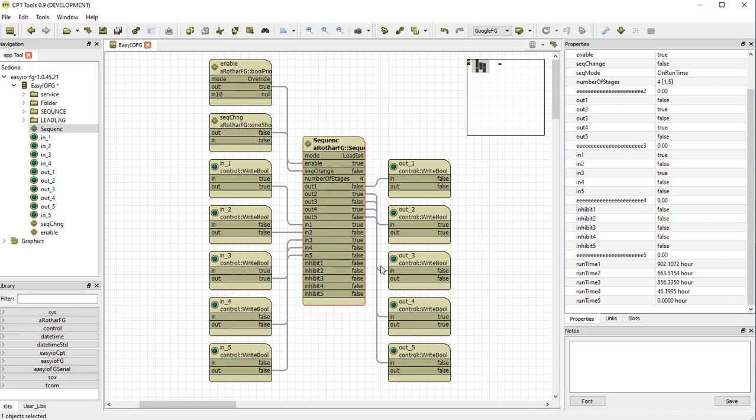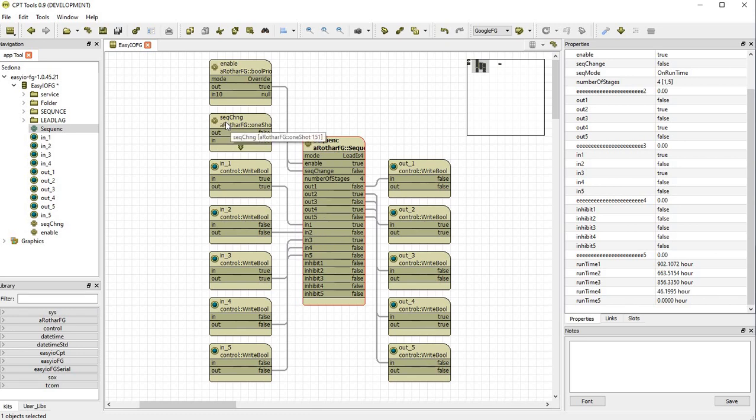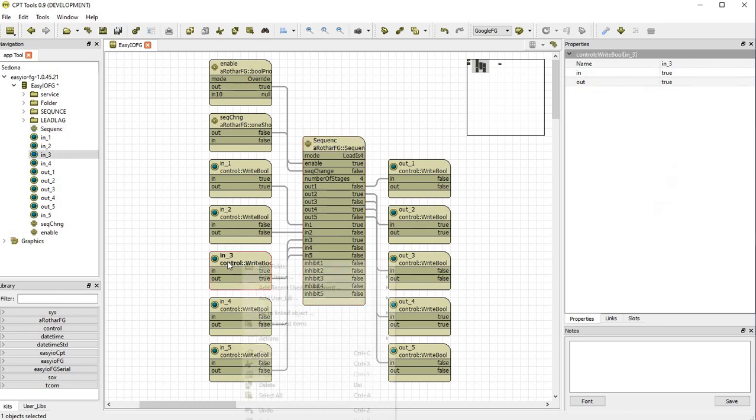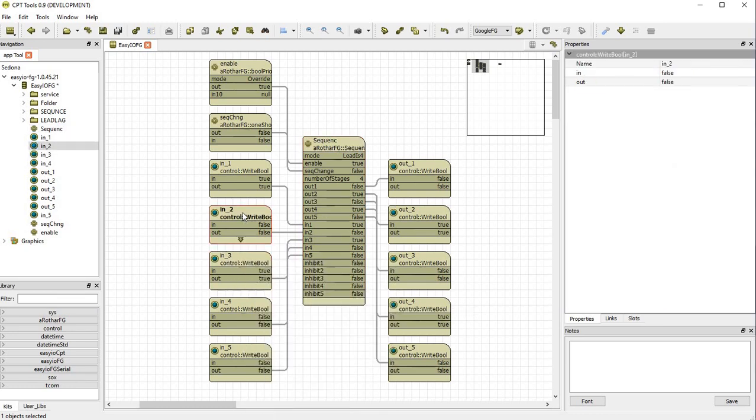And a sequence change will only occur when the input demand changes or it gets a sequence change fire. Otherwise, if there is no change in input and no sequence change, output two and four will run indefinitely. So you could punch in a schedule into the sequence change once a week. That way the system can check. It will also check every time it does a sequence change or a demand change.